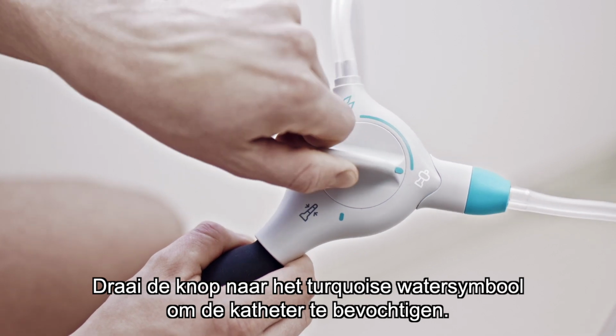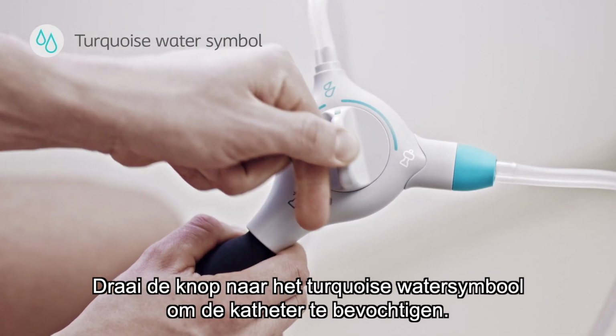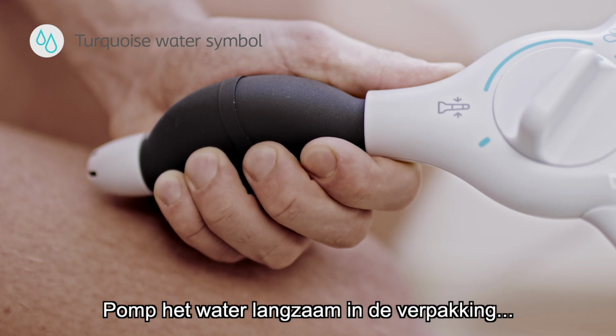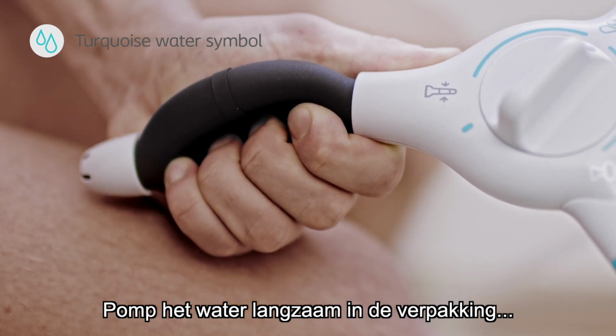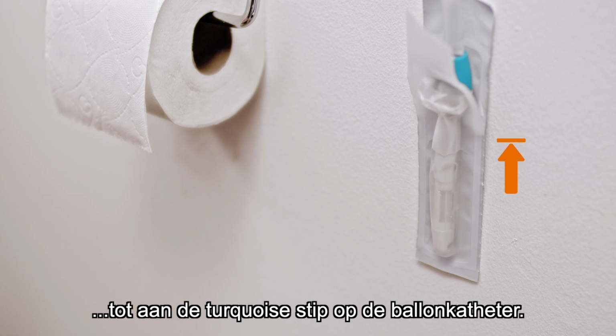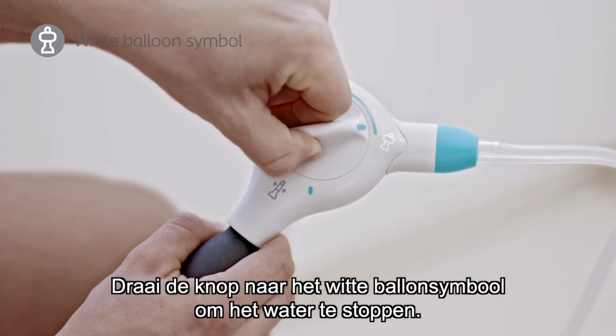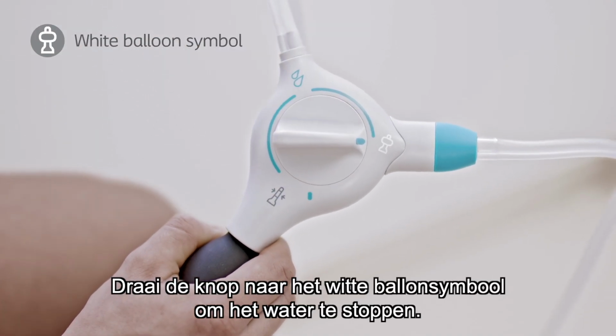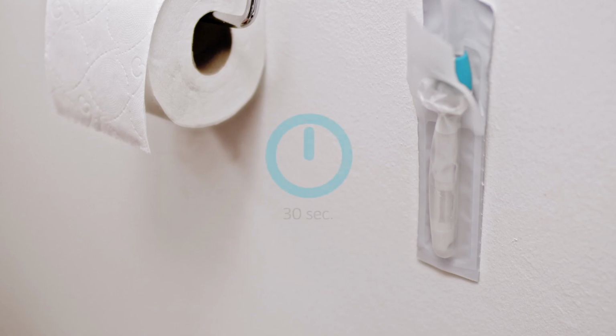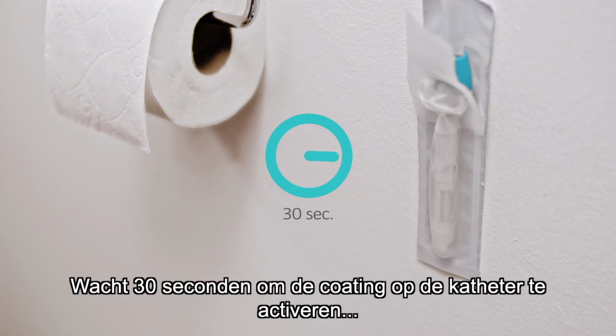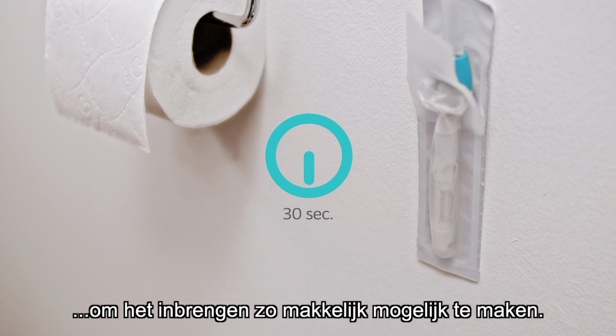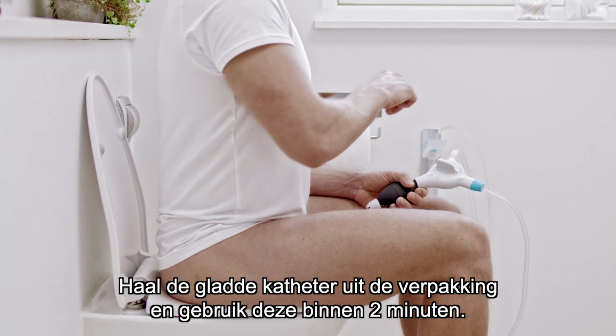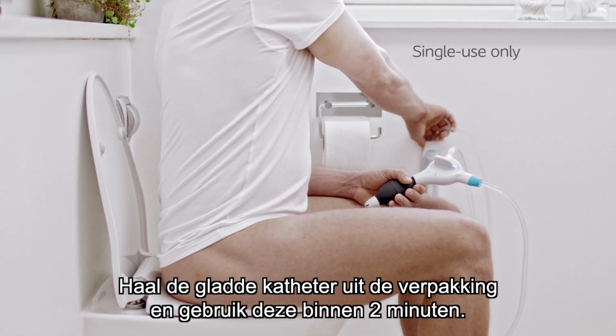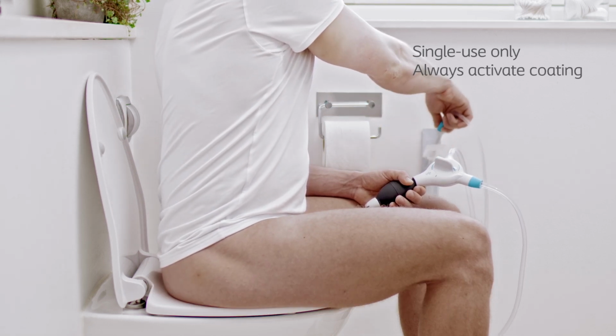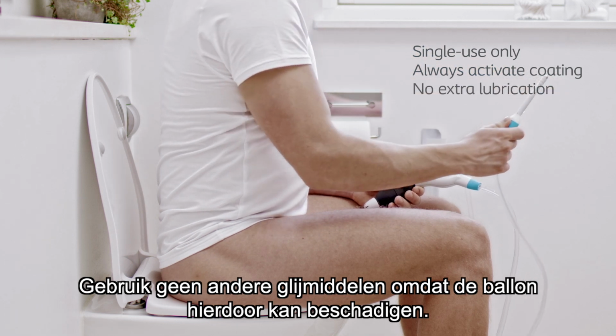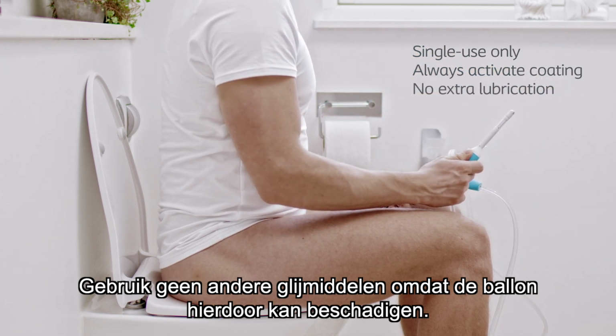To lubricate the balloon catheter, turn the knob to the turquoise water symbol. Pump carefully until the water fills the catheter packaging to the turquoise dot. Turn the knob to the white balloon symbol to stop the water. Then wait 30 seconds for the lubricant on the catheter to be activated so it's easy to insert. Remove the lubricated catheter from the packaging and use it within 2 minutes. Do not use any other lubricants on the balloon catheter, as this might damage the balloon.